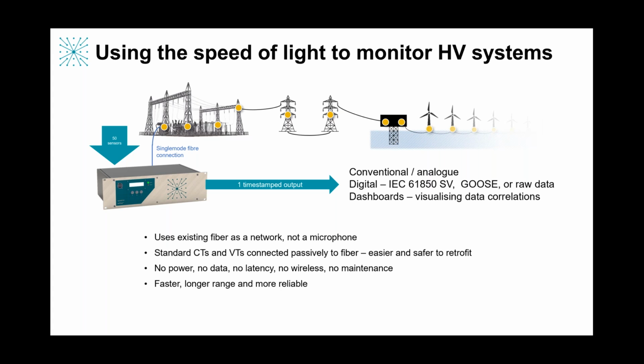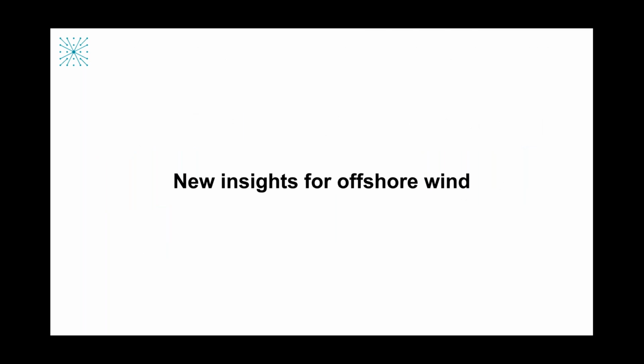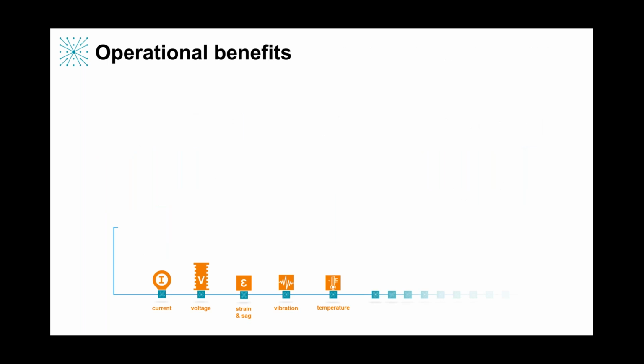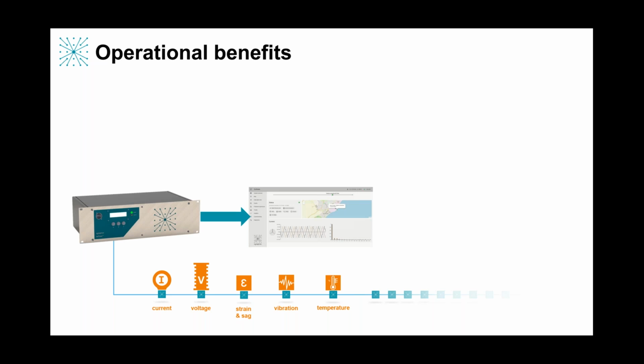In fact, there is no data outside your substation, so it's faster, longer range, and more reliable than any existing technology. And we can measure any combination of voltage, current, strain, vibration, or temperature up to 100 kilometers away from the first sensor to the last at the speed of light through that fiber. And that's important for offshore wind, because effectively this combination of all these different parameters are brought in live into this box, only connected by light through the fiber. And that means we've got instantaneous live representations and visualizations and correlations of what's happening out there back in the control center.